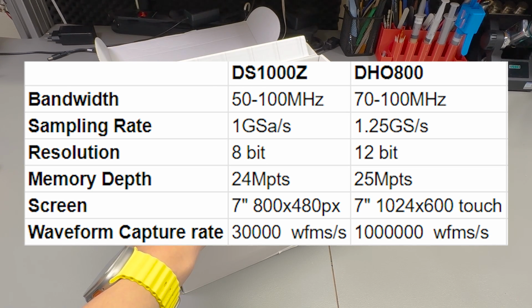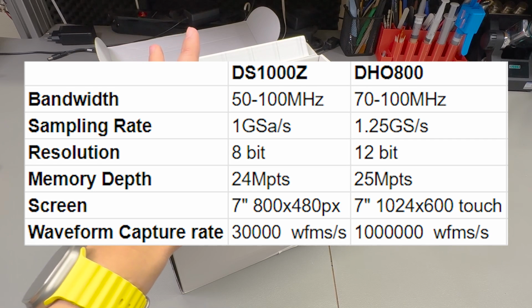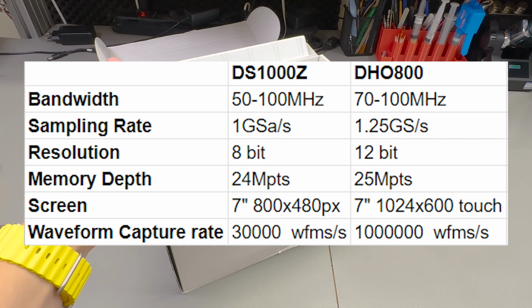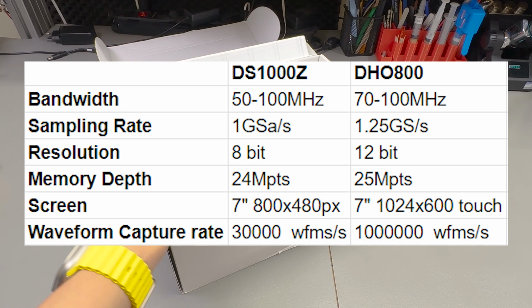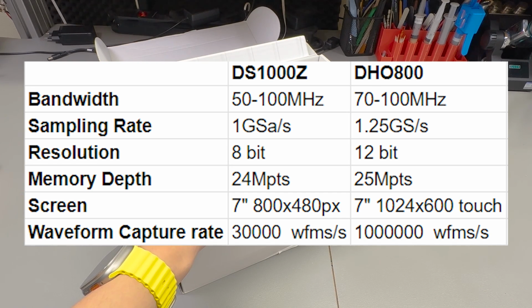The sampling rate has a slight bump to 1.25 gigasamples per second. The vertical resolution was increased to 12 bits, and this is going to be such a huge selling point. It will make a massive difference in the way tiny signals are captured and visualized. Memory depth, again, slight bump up to 25 meg points, and I believe there is a software option to enable 50 meg points. Screen is still 7-inch, but it is now a higher resolution at 1024 by 600 pixels and is a capacitive multi-touch. And the waveform capture rate can now go up to a massive 1 million waveforms per second in the special ultra acquire mode.